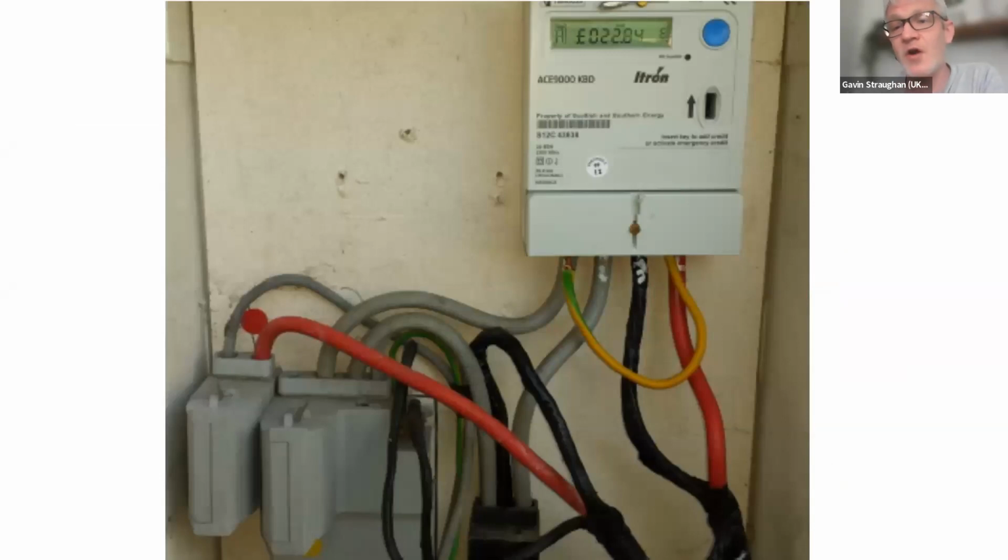This is probably the most common thing you will see when it comes to a bypass electricity meter. Now, the electricity, I don't know if you can see my mouse now, off the cutout here, what you've got is the power coming out here, so that's the secondary fuse on the side here, into the meter. And what happens is it comes in through this wire, goes around the meter, and then back out this red wire here to the consumer unit.